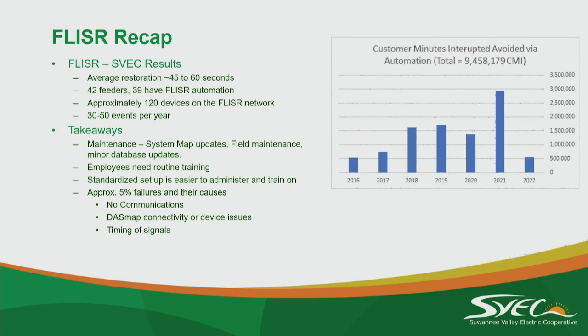When you're doing 20 to 25 devices a year, you're replacing some old hydraulic reclosers that may have been overloaded if you were to backfeed on them with a SCADA controlled device. If you don't pull that off of the map and the map still sees it, it's going to go through and say you're going to overload this recloser, we can't do it.